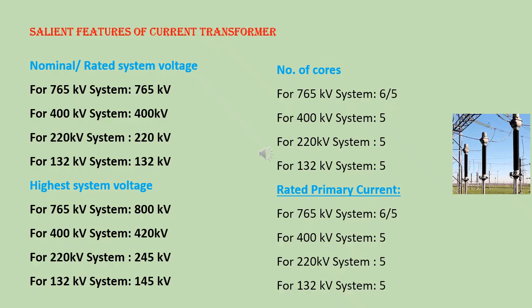In second step, we will elaborate highest system voltage. For 765 kV system, highest system voltage is 800 kV, and for 400 kV systems, highest system voltage is 420 kV. For 220 kV system, highest system voltage is 245 kV. Highest system voltage for 132 kV system is 145 kV.